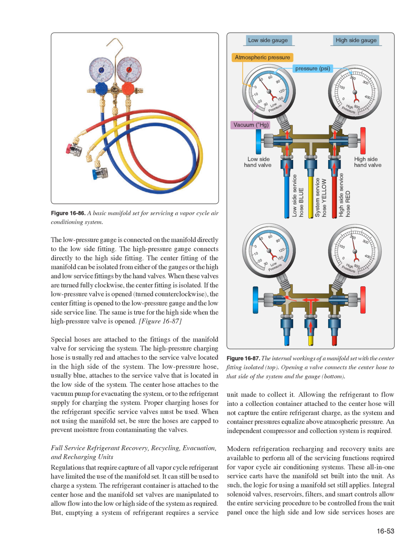When these valves are turned fully clockwise, the center fitting is isolated. If the low pressure valve is opened, turned counterclockwise, the center fitting is open to the low pressure gauge and the low side service line. The same is true for the high side when the high pressure valve is opened.